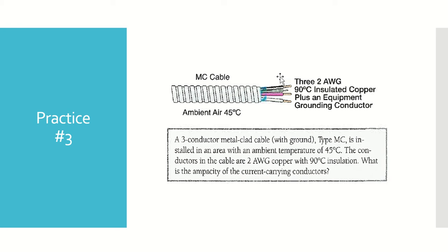So a couple things I wanted to point out. This is going back to what gets counted. So it says where the number of current carrying conductors in a raceway or cable exceeds 3, or multi-conductor cables are installed without a spacing of a continuous length of 24 inches and are not installed in raceways, the allowable ampacity of each conductor shall be reduced. Each current carrying conductor of a parallel set of conductors shall be counted as current carrying conductors. And let's continue on. So this was 3(a).